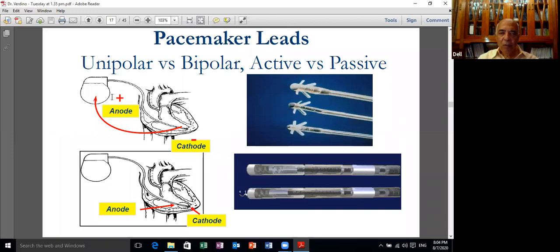Now we move from this to the pacemaker leads. Actually, we have 2 varieties of leads. And in recent pacemakers, you can change the bipolar lead into a unipolar lead under certain circumstances. With unipolar leads, you have the cathode at the end of the electrode, located in the ventricle or in the atrium. It's pacing under the trabeculae of the ventricle or in the atrial appendage or somewhere in the atrium. And because the electrons have to go somewhere, they go to the pacemaker can, which is a titanium can, hermetically sealed and containing the components of the pacemaker.